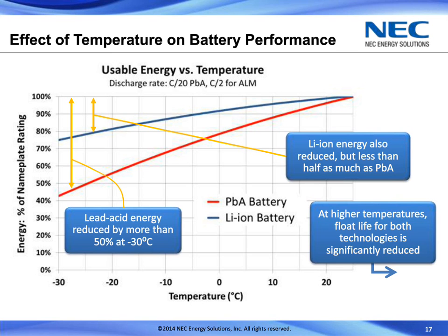At higher temperatures, the capacity actually does pretty well for both technologies, but the float life and, to some extent, the cycle life of both technologies is significantly reduced. So at lower temperatures, you lose capacity. At higher temperatures, you lose life, and that's how temperature affects these batteries.